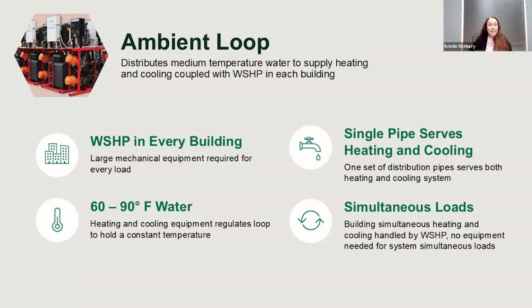The next thing to talk about is ambient loop, which you may have heard about—people have a lot of misconceptions about it, and this could easily be an entire topic on its own. Basically what it does is distribute medium temperature water, not medium temperature hot water, somewhere around 60 to 90 degrees. There's a loop that goes around your campus distributing that, and from there it interacts with a water source heat pump in every single building.